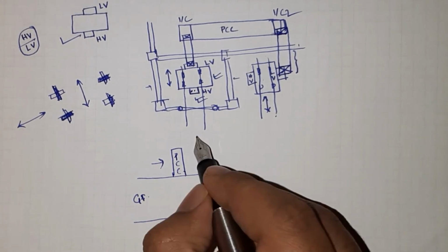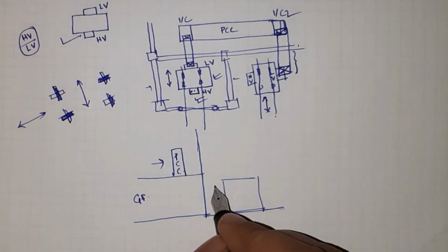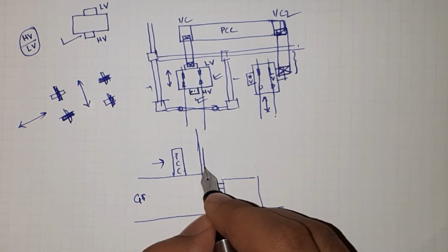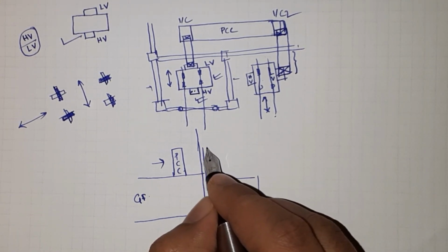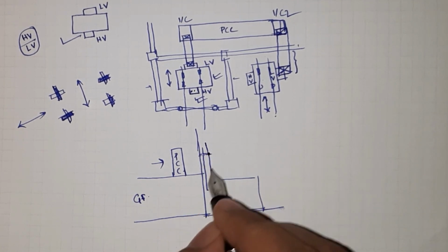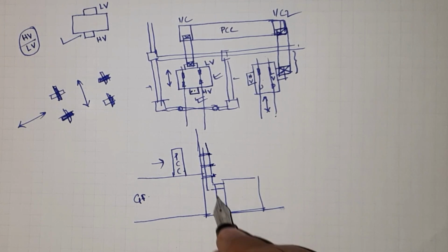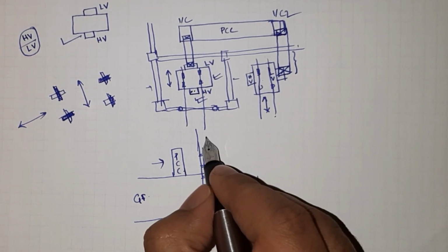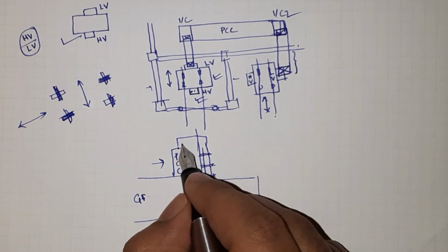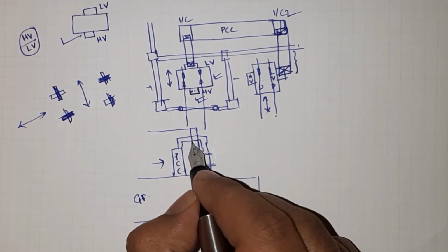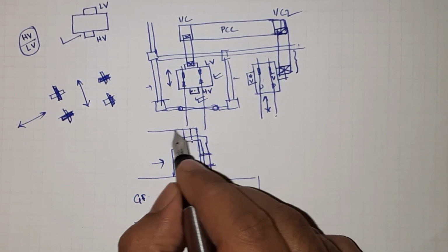In this arrangement I will take the bus duct from here and take support from the wall to climb. The bus duct will be supported at the wall for the riser, and at the bottom it will take support from the bottom, and from there it will jump down to the PCC, and this portion will be supported from the ceiling.